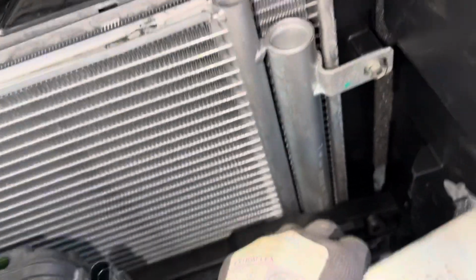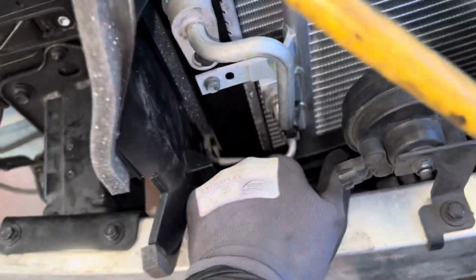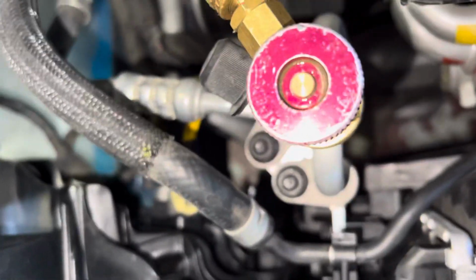Let's follow this liquid line. Where is that liquid? Okay, the liquid line out of the bottom of the condenser. Thank God it's out the bottom. It doesn't confuse people. And I'll just let you see to make sure there's no other pipes. Here on the other side, there's no pipes down. There's nothing coming out of the condenser on this side. It's just straight up receiver over here. Appears to be liquid line here, and let's see if we could follow it. Can we follow that line? Yes, I see it. That line at the tip of my finger going down.